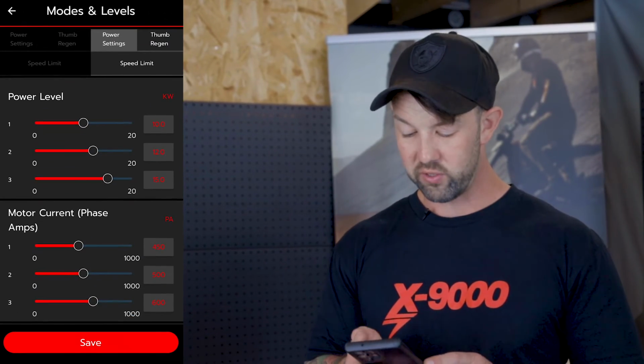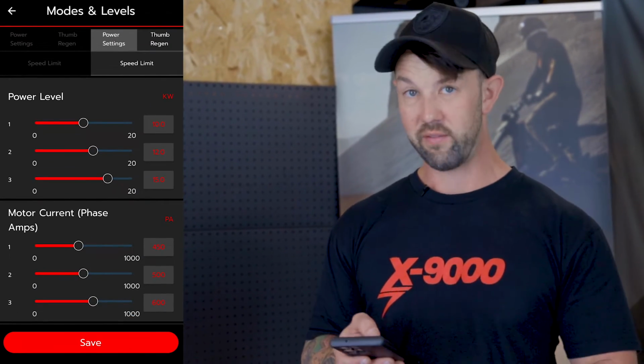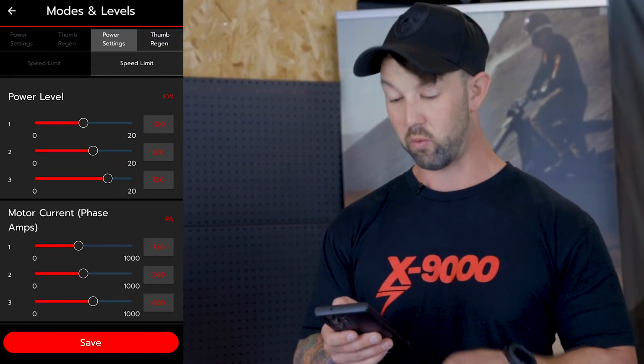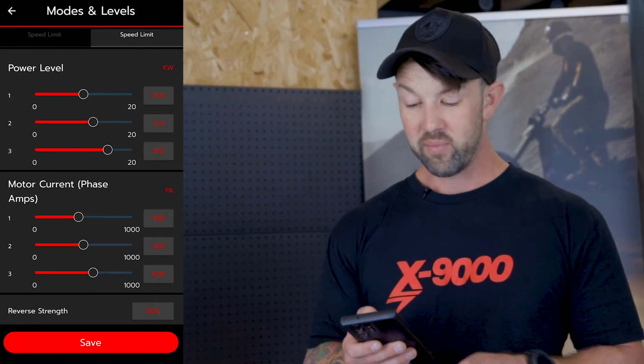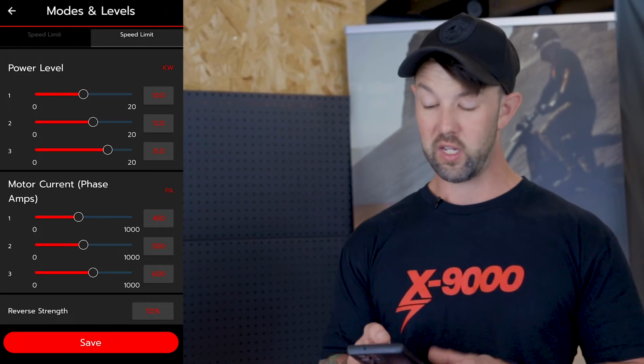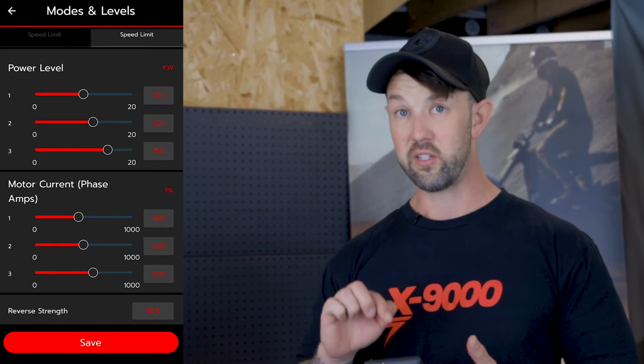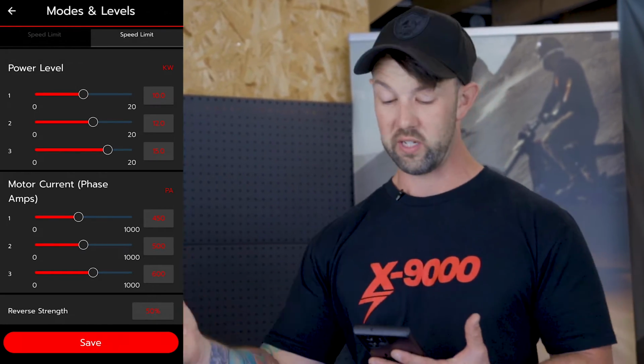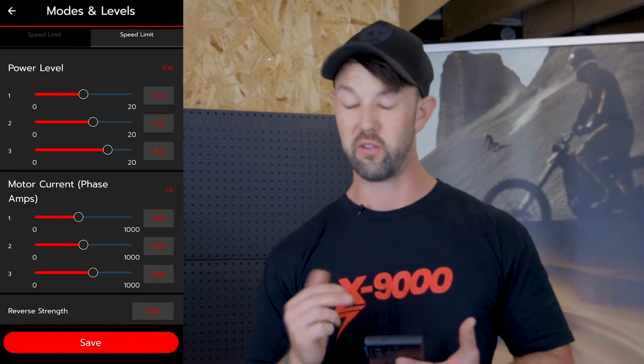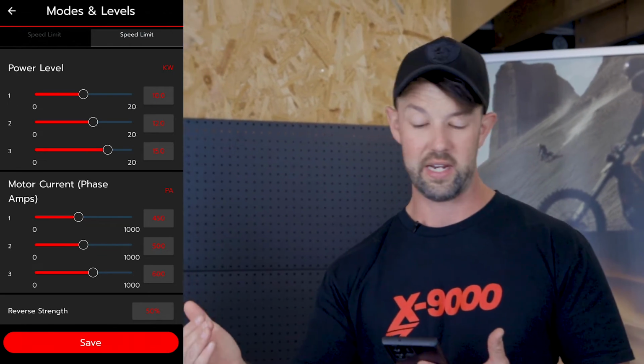Now we're on to modes and levels. If you select a 72 volt battery and a stock harness, this will pretty much be set where it needs to be. I'm happy with 10, 12 and 15 kilowatt. Just remember that when you set these values, the peak value could exceed this - so for a split second, if you set to 15 kilowatt, you might actually hit 17.